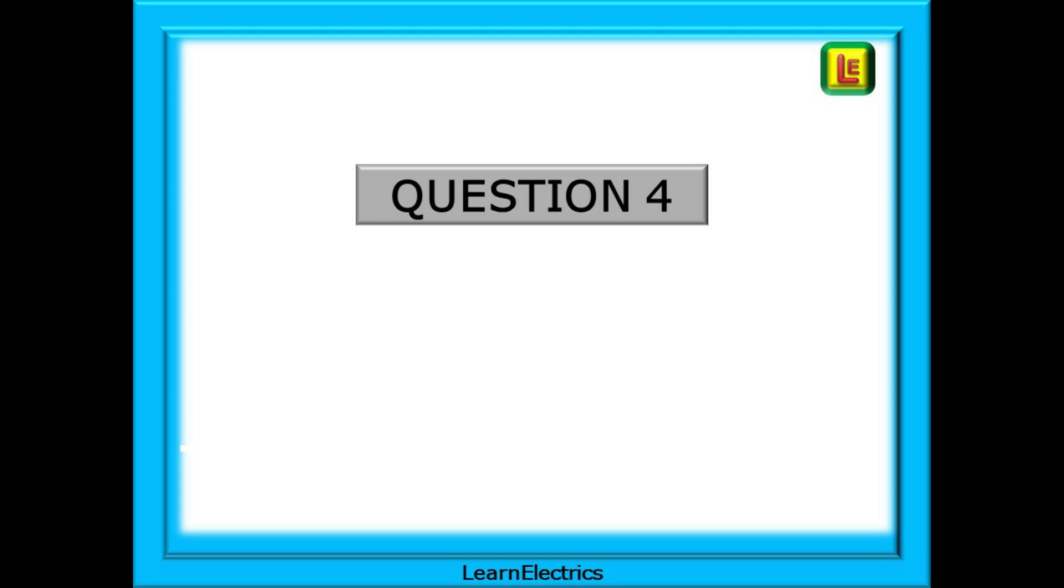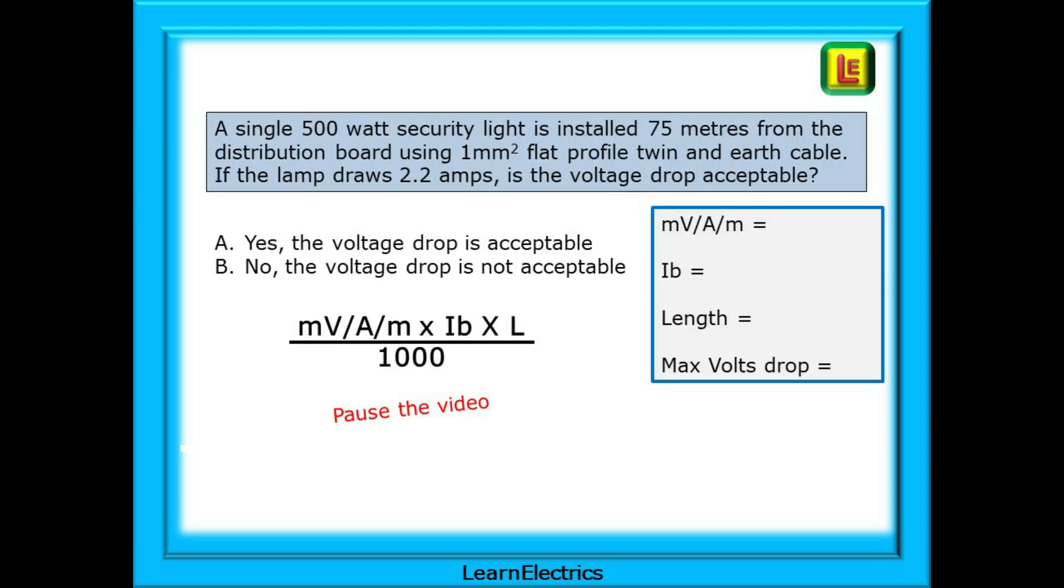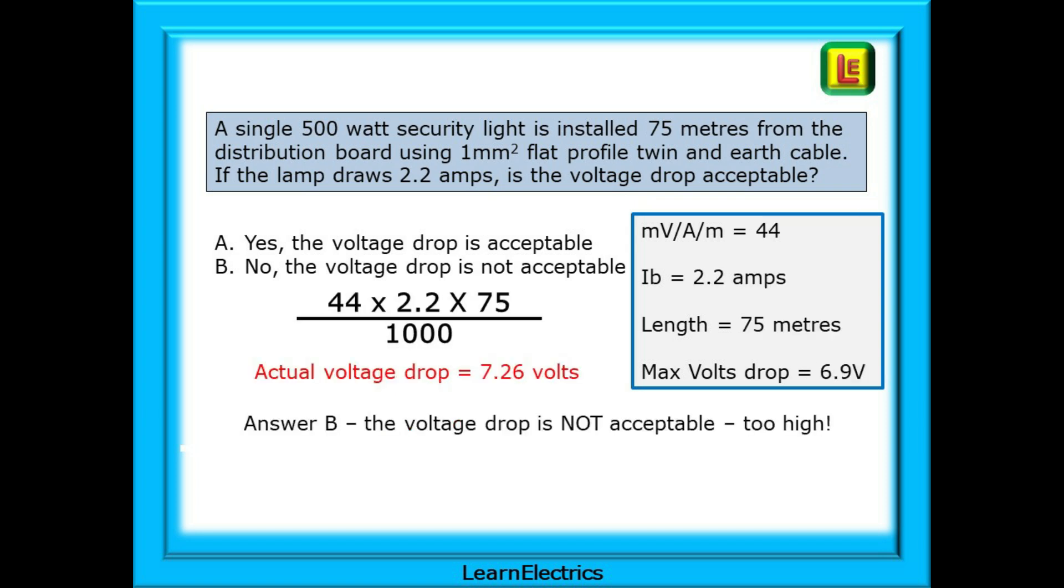Question 4 is about lighting circuits. A single 500 watt security light is installed 75 metres from the distribution board using 1 square millimetre flat profile twin and earth cable. If the lamp draws 2.2 amps is the voltage drop acceptable? And just two options to choose from. Pause the video and go through the answer process. The actual voltage drop is 7.26 volts and this is above the permitted maximum of 6.9 volts for lighting circuits. Therefore choose answer B. The voltage drop is not acceptable.